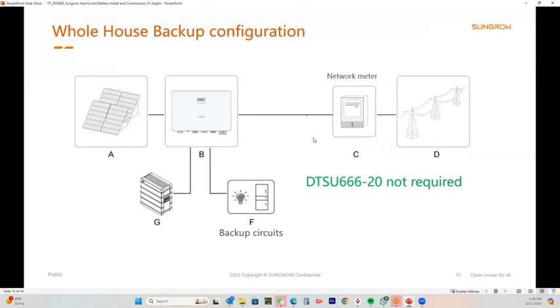Okay, a whole house backup. Now this is what I was talking about, the pass-through. With the 8 and the 10 and the 15, 20, 25T, they are capable of what we call the whole house backup configuration. This is where, as in this situation here, the entire house loads are connected to the backup circuit. Now this is where you get the 63 amps, because it could be night time and the battery could be totally discharged, and if you've got that fully loaded up to 63 amps, the 63 amps is going to come through that AC cable and out to the loads. Now if you do this configuration here, you actually don't need to install a meter. The reason for that is the inverter actually will do all the metering for you. So this is the whole house backup.